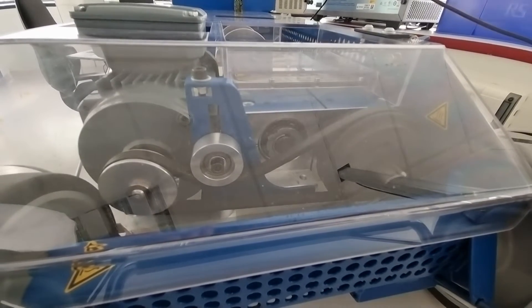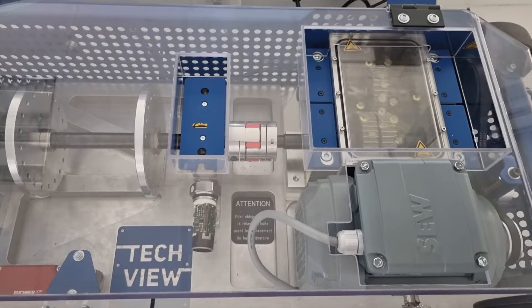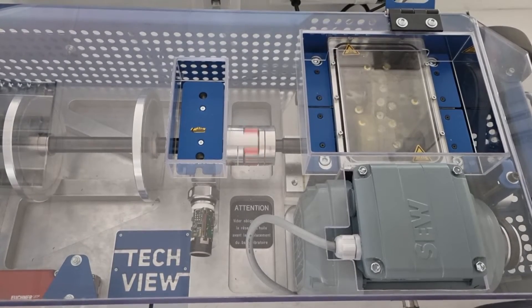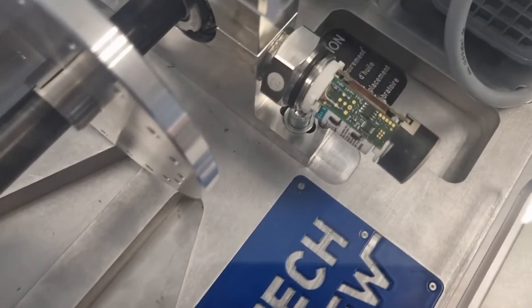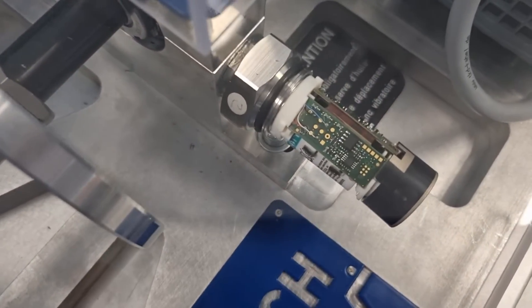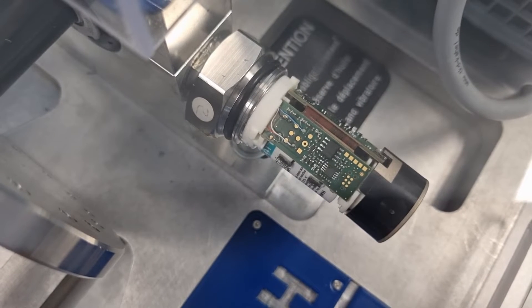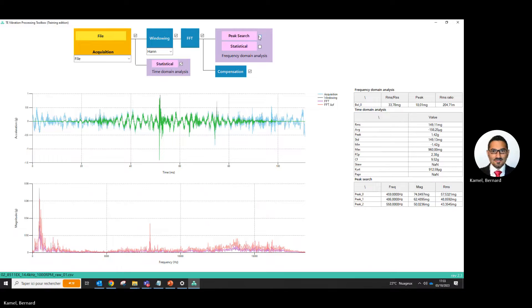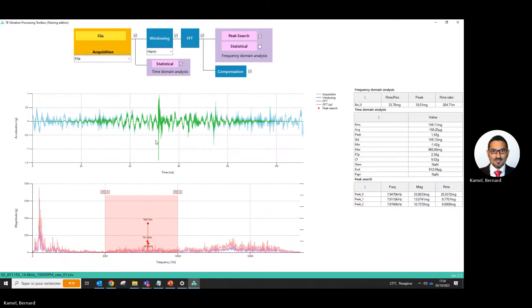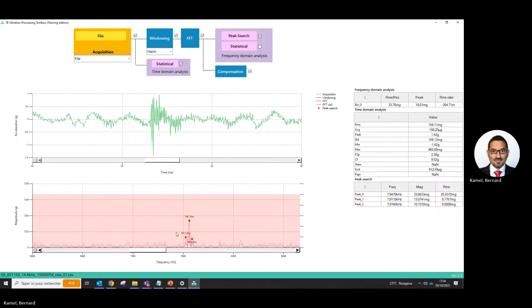Vibration data is mainly collected using an accelerometer. Once the data is taken, the readings are processed at the edge to extract smart data from time waveforms such as RMS, peak-to-peak, and acceleration in the time domain, and is also used to extract peaks from fast Fourier transform in the frequency domain.